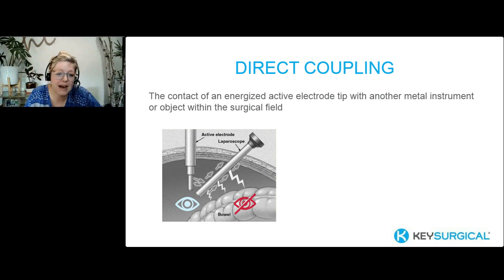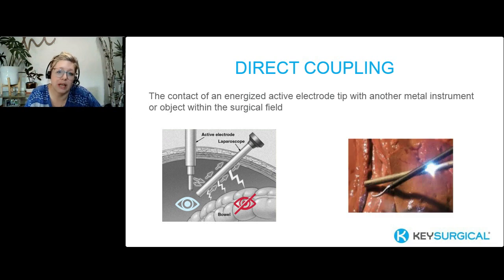What happens is now we've created another active electrode. We've energized something else. So you can see it in both of these images. The blue eye is, we can see this. This is in our surgical field. But that red eye is, now we have the active electrode touching a laparoscope, and that laparoscope now is energized and can burn adjacent tissue, right? It can cause a tissue effect in an area we don't want to, and that we can't see, and that we didn't intend.